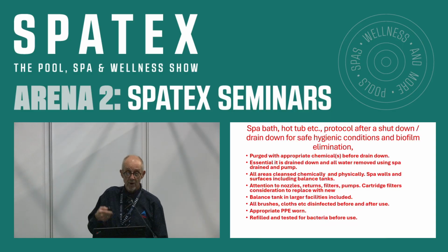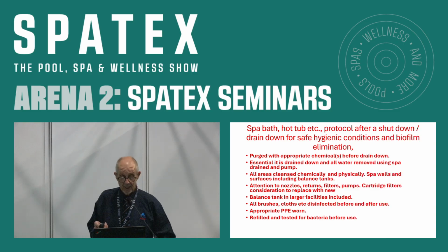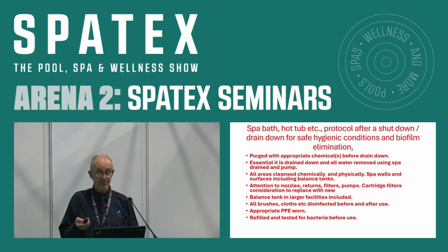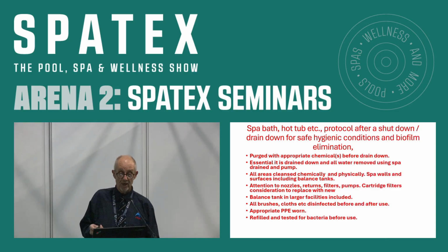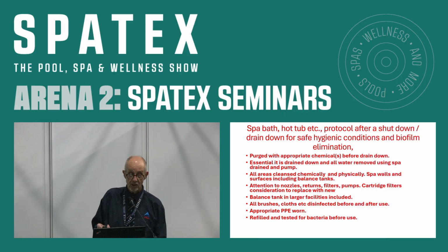Okay, spa hot tub protocol after a shutdown. Drain down for safe hygienic conditions and biofilm elimination. Purge with chemicals. Essentials: drained down and all water removed using spa pumps, drained and pumped out. All areas cleansed chemically and physically. Walls, surfaces, balance tank. Attention to nozzles, returns, filters, pumps.